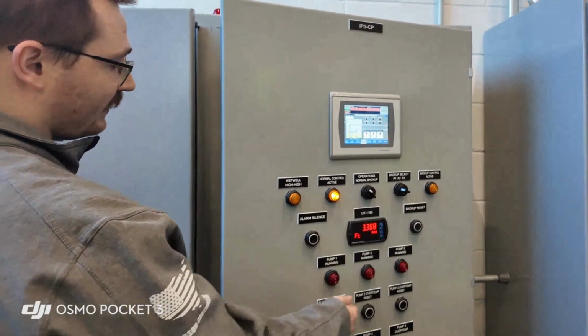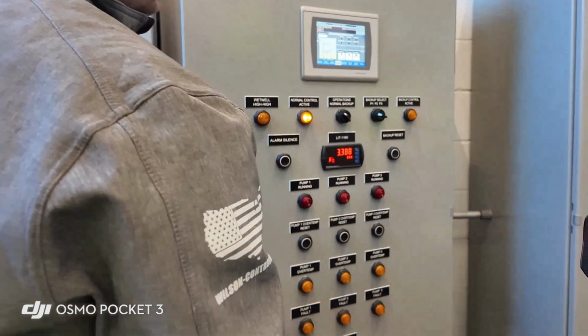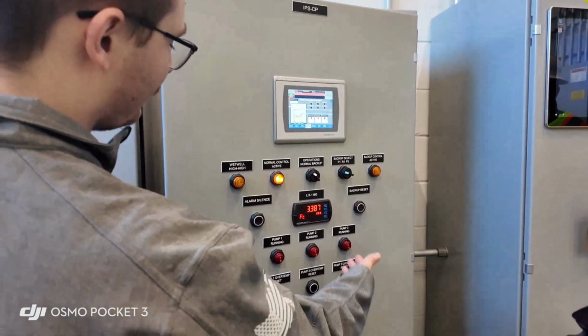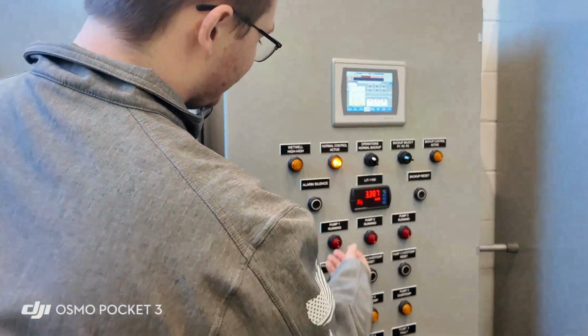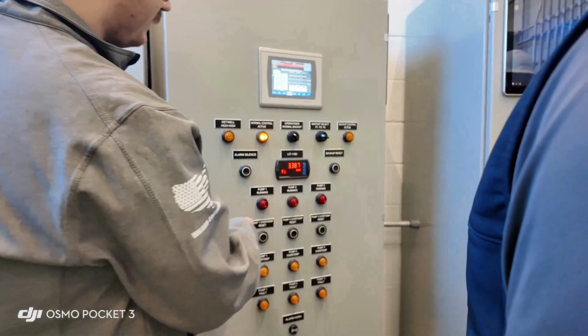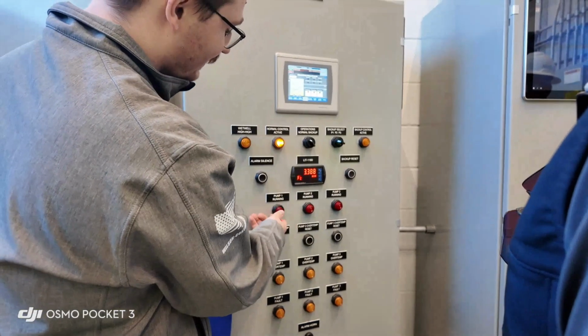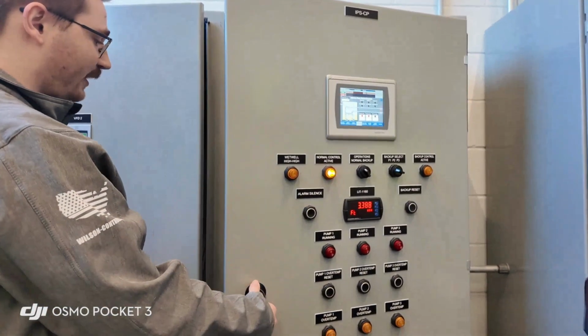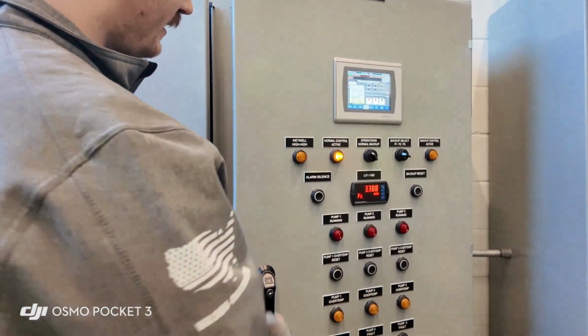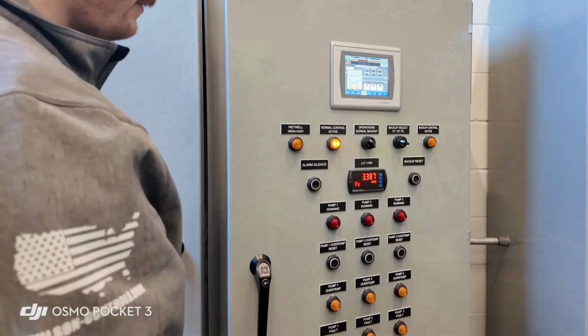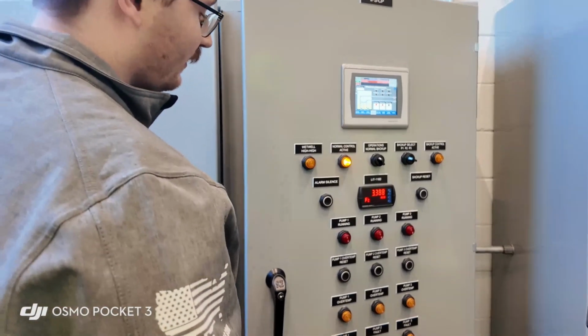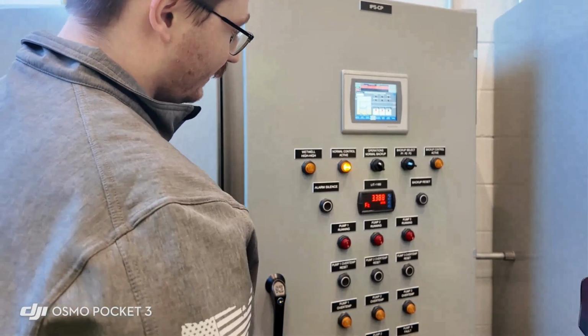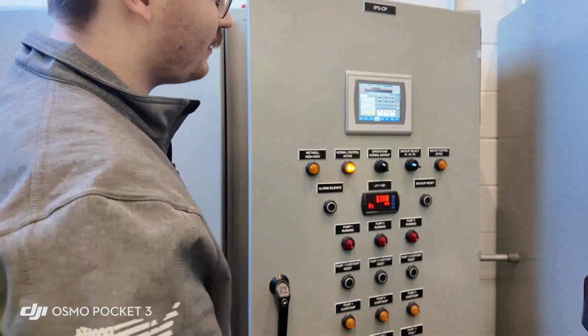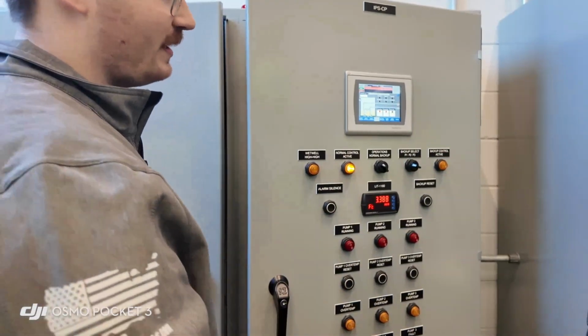We have indicating lights for pump run statuses. Future design is supposed to be 3 pumps, so we just included that. So we got run status lights. On the screen, it's green up here, but it's red down here. These have MiniCAS in here for seal and overtemp protection. If you have an overtemp alarm, it'll show up over here, and it'll also come up on the screen as a common alarm, and it tells you what is common on it.